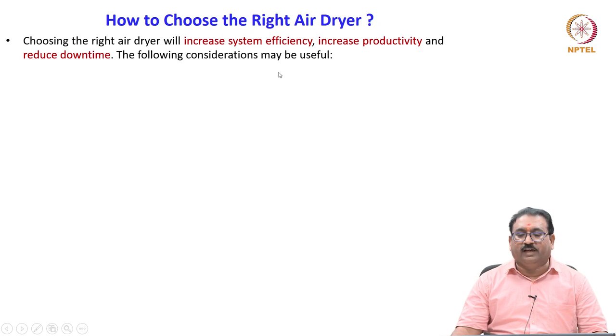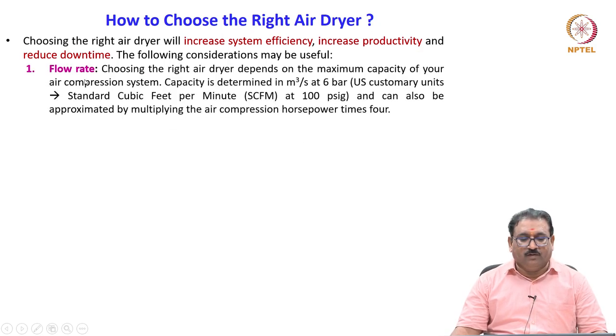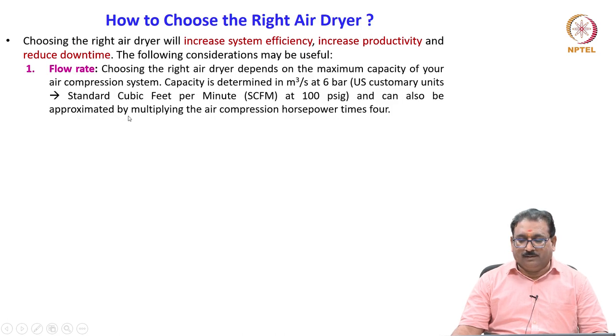Choosing the right air dryer depends on the maximum capacity of your air compression system. Capacity is measured in m³ per second at 6 bar, or in US customary units as standard cubic feet per minute (scfm) at 100 psig, and can also be approximated by multiplying the air compression horsepower by 4. The right air dryer will increase system efficiency, increase productivity, and reduce downtime.